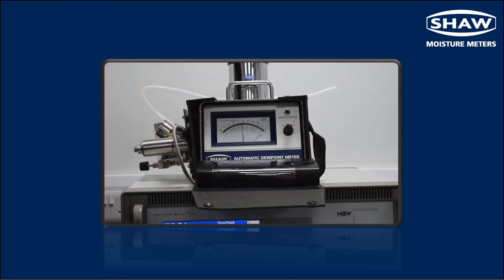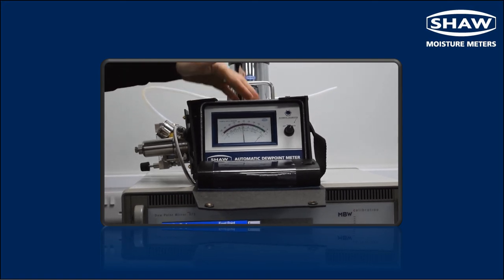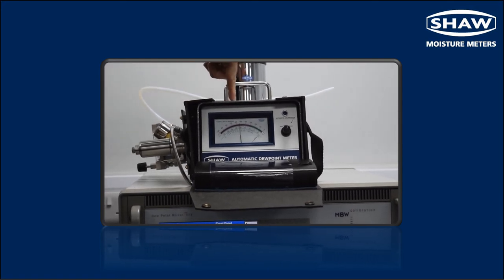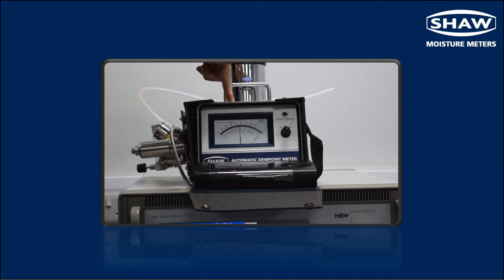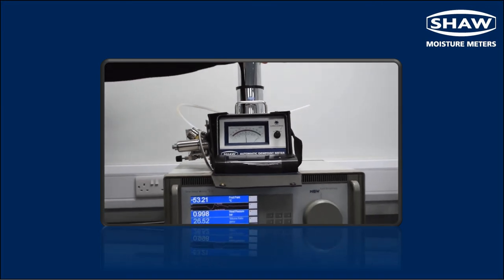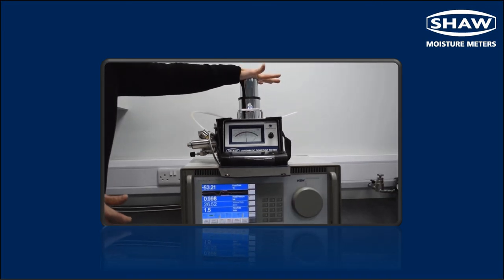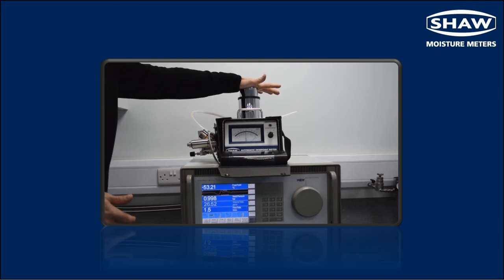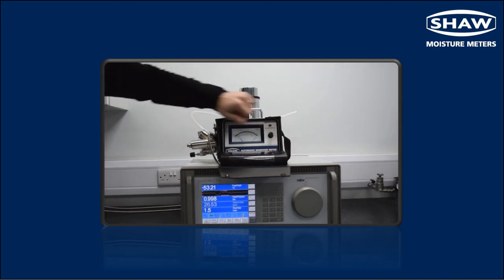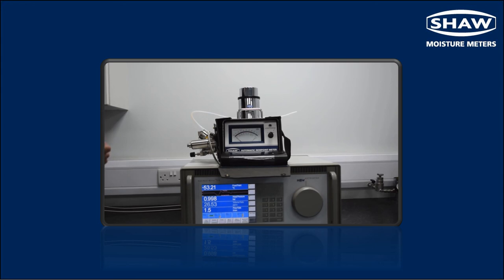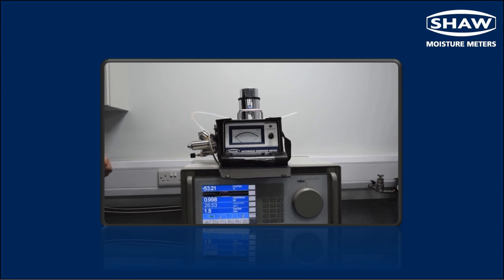Right, so after five minutes the SADP has come into equilibrium with the process gas. The needle has stopped moving so we're ready to take a reading. Once that's done we can put the sensor back in the dry down position, turn off the dew point meter, and then we can disconnect it and move on to the next point.